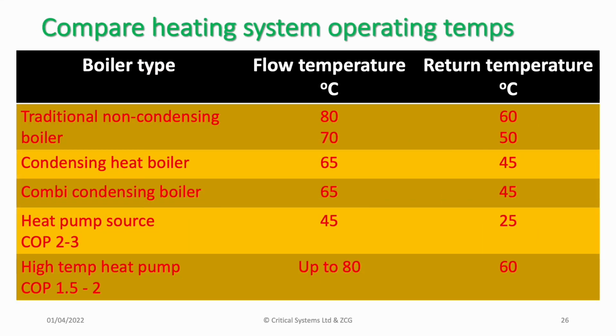I show this table from my previous talk, and it illustrates the impact of different flow and return temperatures. So I just want to focus on the condensing boiler line. Classically, a condensing boiler will have a flow of 65 degrees and a return temperature of around 45 degrees to ensure condensing conditions. And a heat pump will have, in the heating system, a flow temperature of 45 degrees and a return temperature of 25. It is possible to select high temperature heat pumps, but they tend to have much lower coefficient of performance.